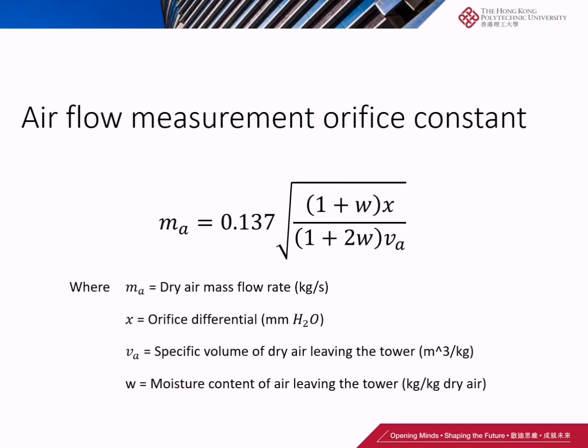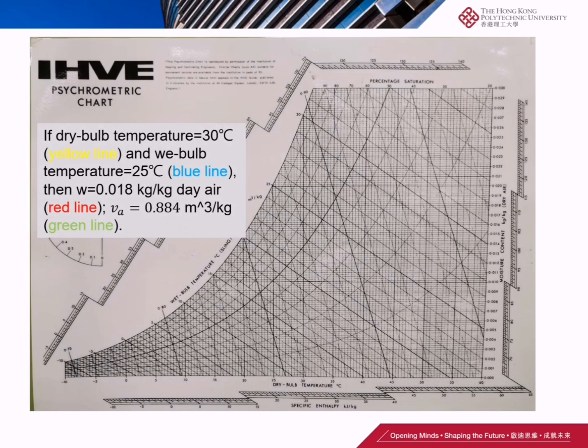In order to calculate the dry air mass flow rate, we need to use the psychrometric diagram to find out the specific volume and moisture content. For example, if we know the dry bulb temperature and the wet bulb temperature, we can use the red line to find out the moisture content and the green line to find out the specific volume.